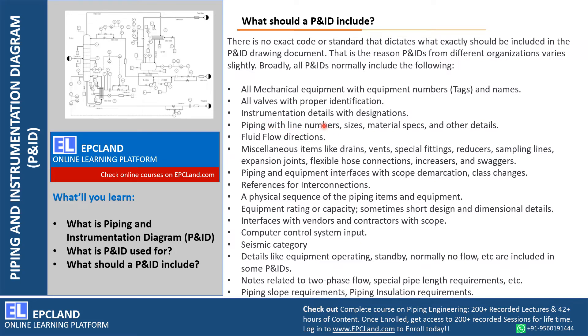The pipeline line number includes line size, piping spec, fluid code, insulation, and insulation thickness. Flow direction is also shown — how the flow is moving from one equipment to another — which helps during startup, operation, and other activities. There will also be miscellaneous items such as drains, vents, special fittings, reducers, sampling lines, expansion joints, flexible hose connections, and expanders — all represented in the form of symbols as they are an integral part of any piping system.